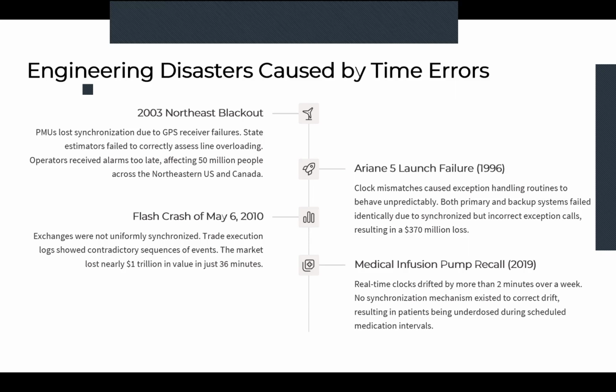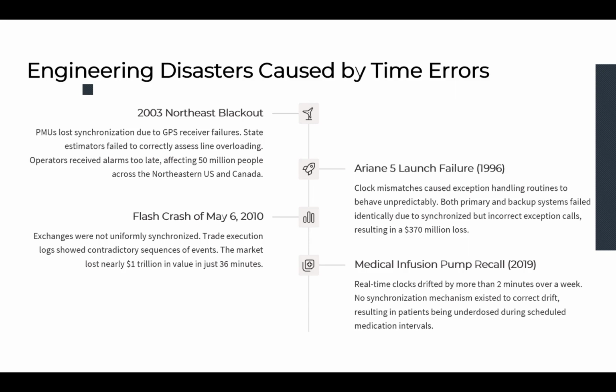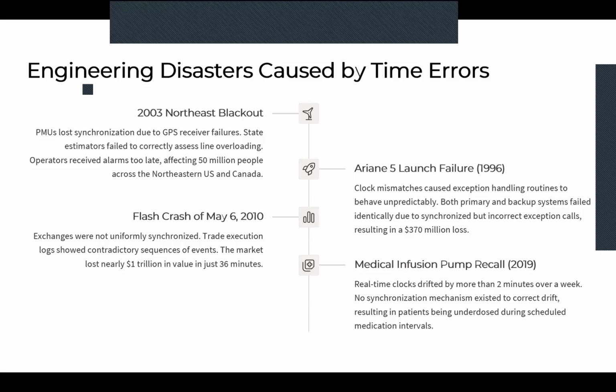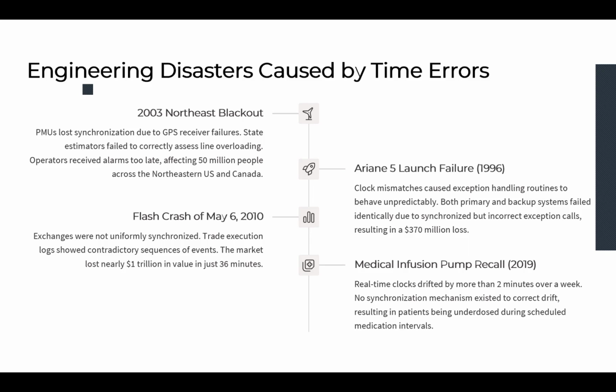If we don't have an accurate time, the phase angle errors would accumulate. The state estimators, which calculate the system stability, received false data or incorrect input because of that time drift. So operators received alarms too late. All that would make for a huge misleading in the protection system, which in that specific case resulted in full instability of the system, and it was a full blackout in the Northeast power grid in the US.